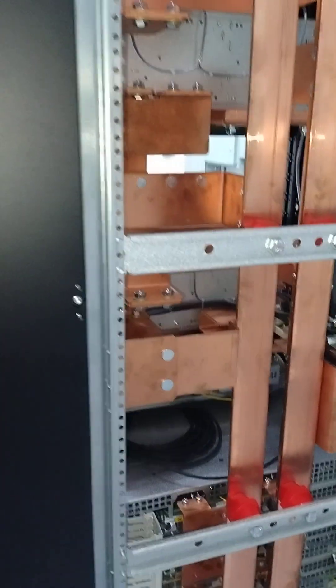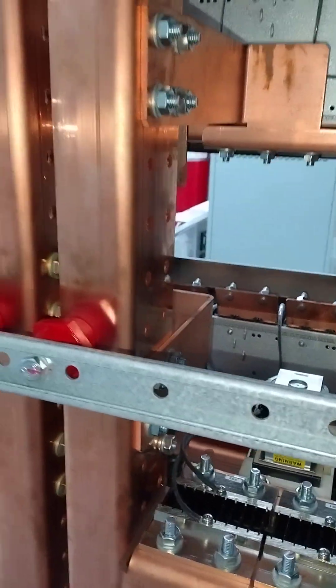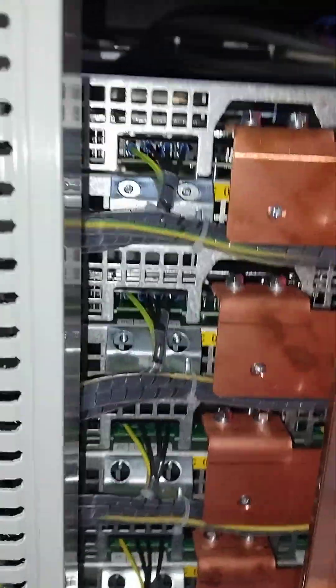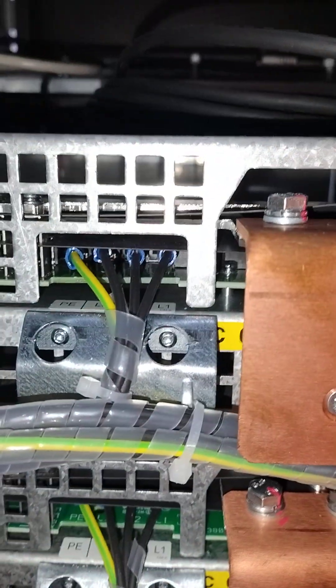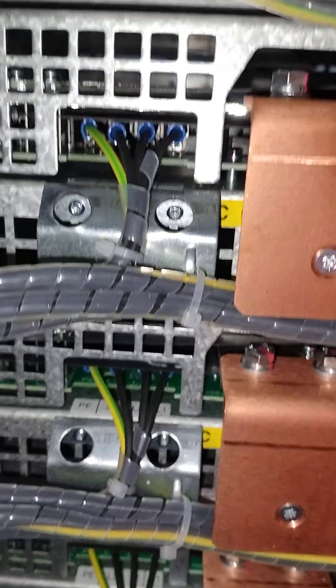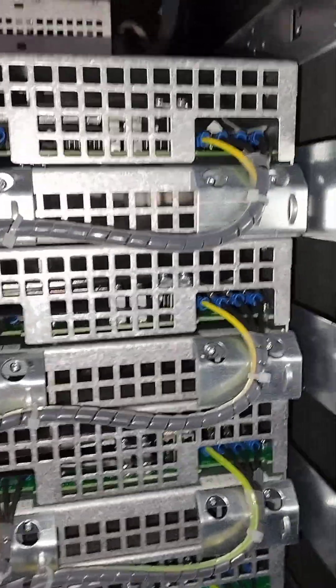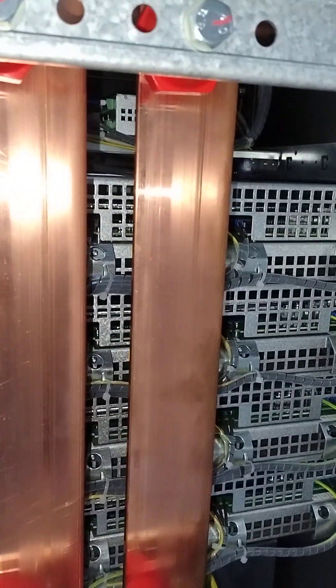What you see here is the back of a rectifier cabinet, which is basically a huge DC bus bar. These are the two bus bars, and these are the rectifier modules. That is the output DC voltage they receive. DC power from here is a modular type of system — you put different modules in and they give you an output DC supply. At the back, these are the two positive and negative terminals.